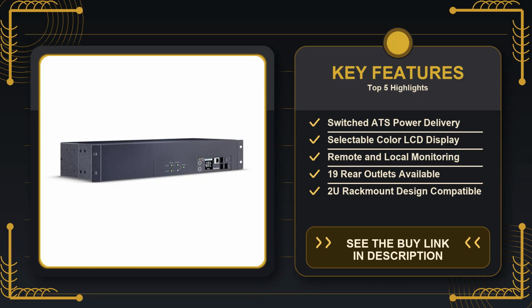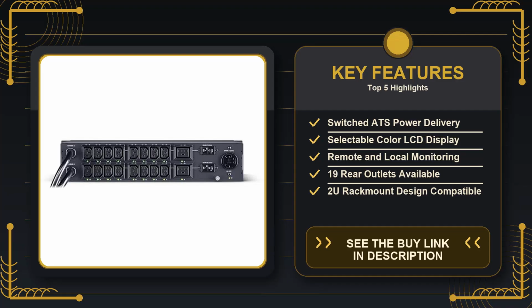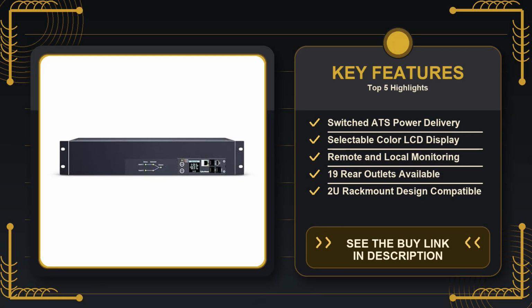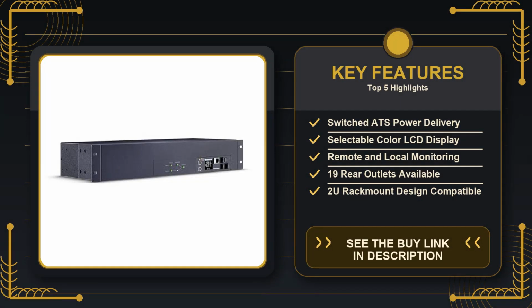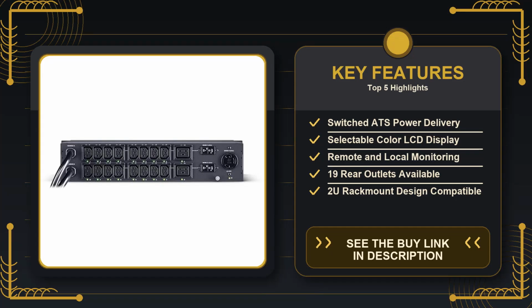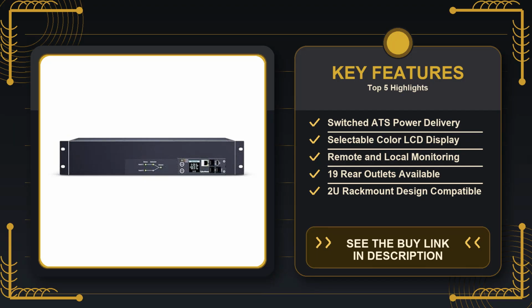Let's talk about the outlet configuration first, because that's where the practical rubber meets the road. On the rear you get 16 IEC C13 sockets, 2 IEC C19 sockets, and a single NEMA L6-30R. For most IT setups that means you can plug in standard server power cords, C13, a few higher draw devices like a small UPS or a high-performance switch, C19, and you have the L6-30R for a beefier input like a larger UPS or a dedicated PDU feed.